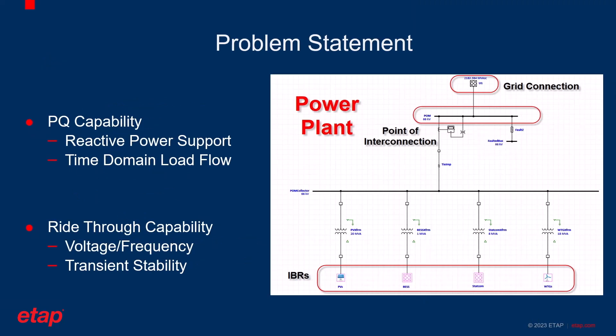In terms of the problem statement, as part of the grid code requirements, power plants are usually mandated to support a certain level of reactive power with respect to their active power levels and the voltage level at the point of interconnection. This study is usually done in time domain load flow analysis.